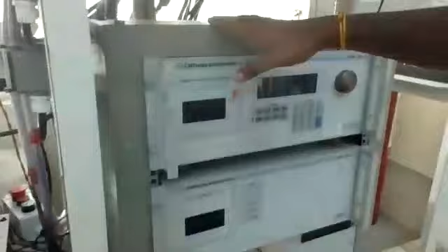And for this, the power supply comes from this California Instruments unit. One significant thing about this California Instruments device is that you can control the frequency and voltage from 0 to 500 volts AC, both in AC as well as DC - I can program it. This has a rating of 5 kVA, that is 5 kilovolt-ampere, so it's capable of providing that much power. This is how we normally have the power source for instrument testing.